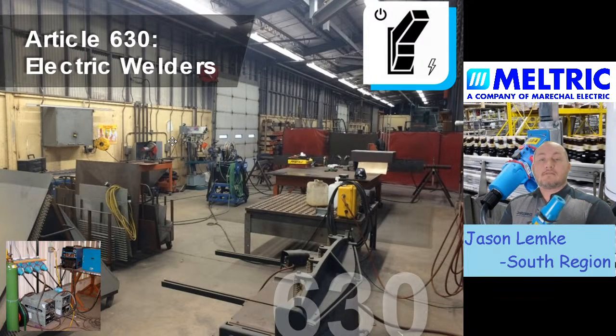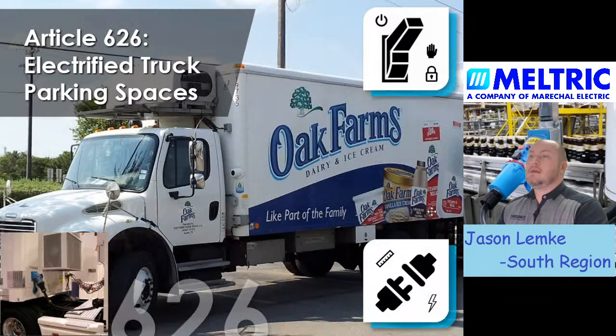That makes this device a perfect disconnecting means for electric welders, because it's not only a plug-in receptacle, and electric welders like to move around shops, but it's also a switch. So you can comply with the National Electric Code for a disconnecting means. Maybe another one might be electrified truck spaces as well, where we have a requirement of the disconnecting means being a switch as well. In addition, it has to be readily accessible and lockable.